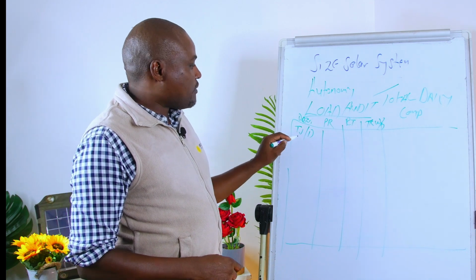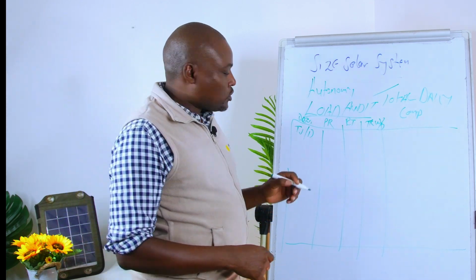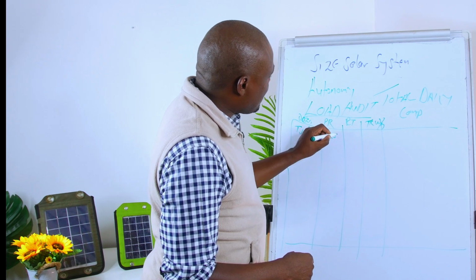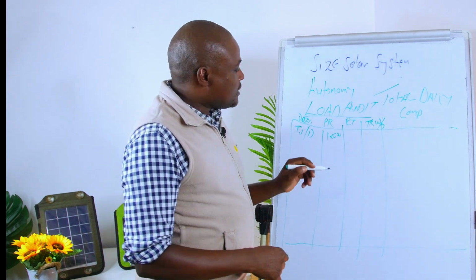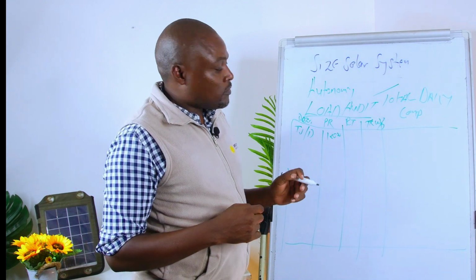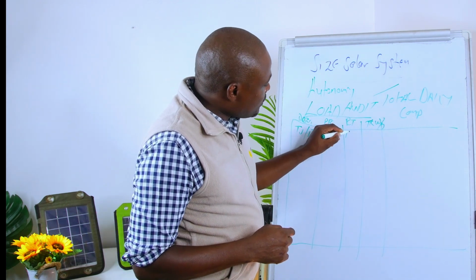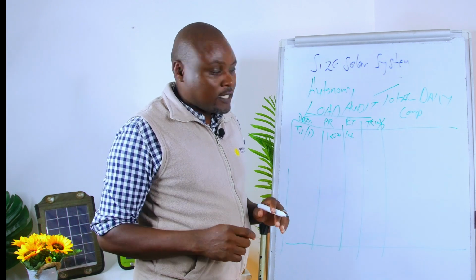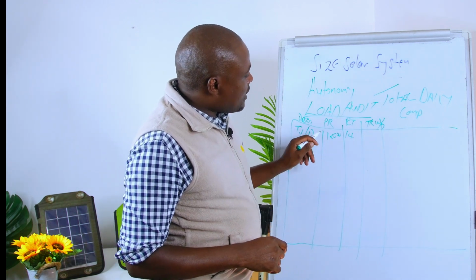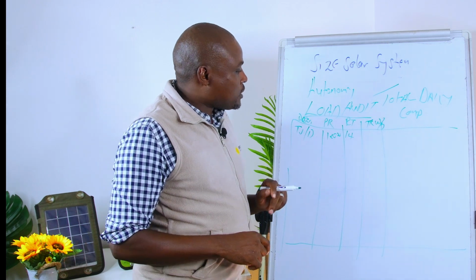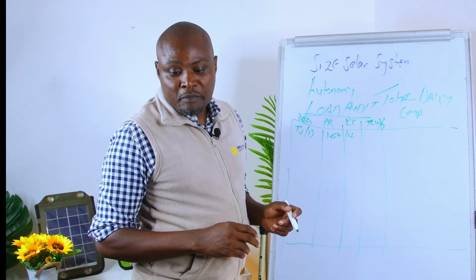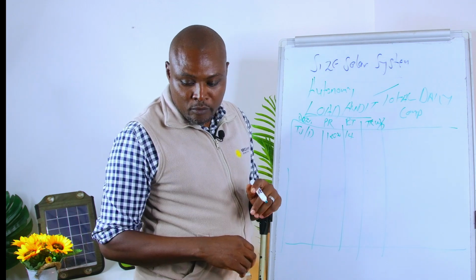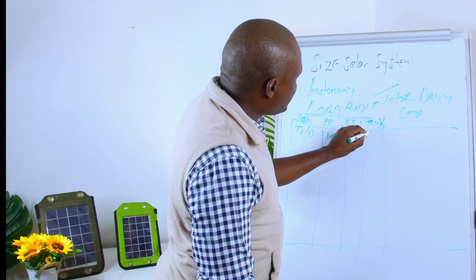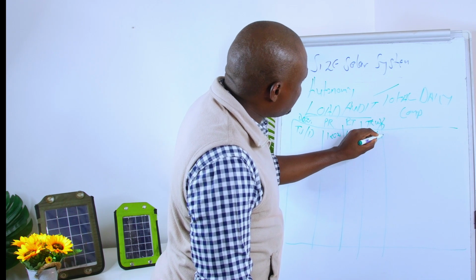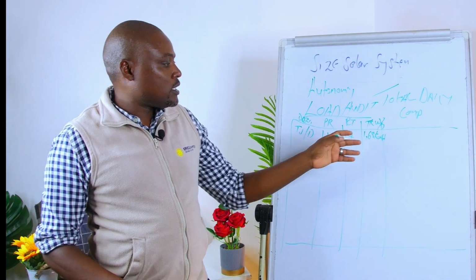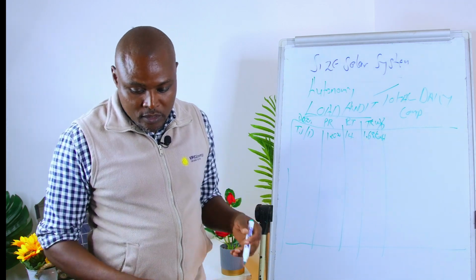If you have a TV and a decoder consuming about 120 watts, and you want to operate it for, say, 14 hours inclusive of day and night time, then you calculate 120 watts by 14, which gives the kilowatt hours per day used for this equipment. In this case, it's 1.68 kilowatt hours, or 1,680 watt hours, whichever way you want to put it.